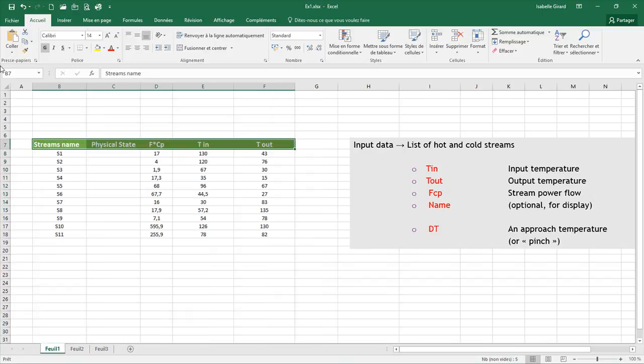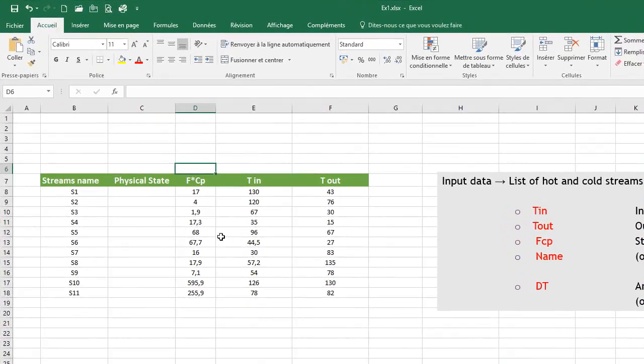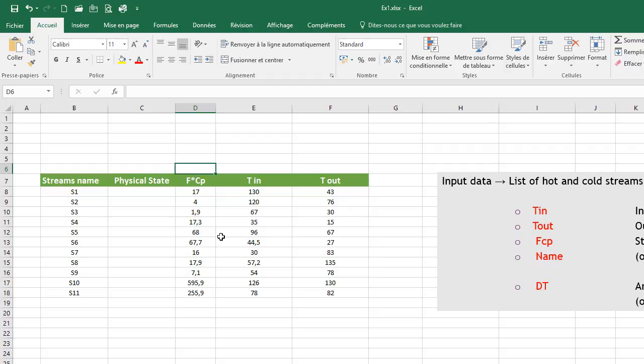After you enter your data, you will need the last input data, which is the pinch. It is the minimum difference of temperature between a cold stream and a hot stream. The more the pinch decreases, the more the heat recoverable increases, but the more the exchange surface may increase too.